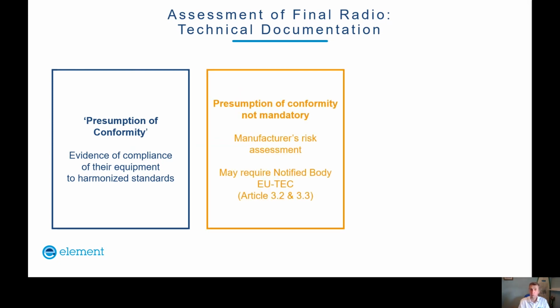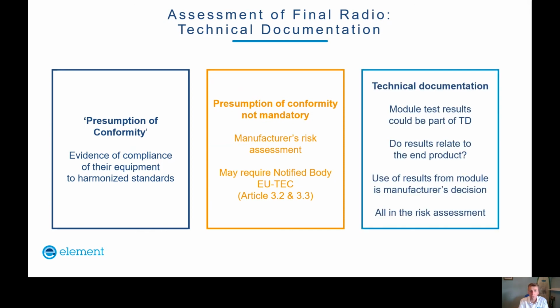If you don't have presumption of conformity, or if the standard you're using isn't harmonized, then remember you will need a notified body's type examination certificate. Actually, a lot of people do ask for the notified body certificate when installing modules anyway, just to get some extra confidence. The technical documentation of the end product must include all aspects of it, and that includes the radio, because you are fully responsible for that radio now.